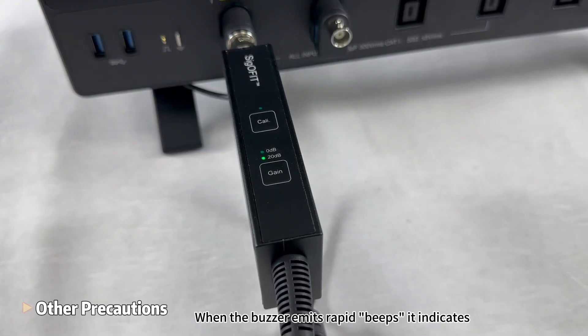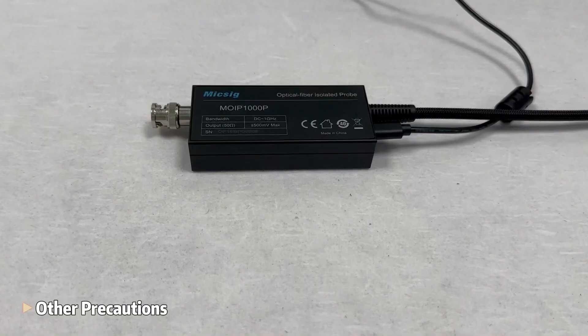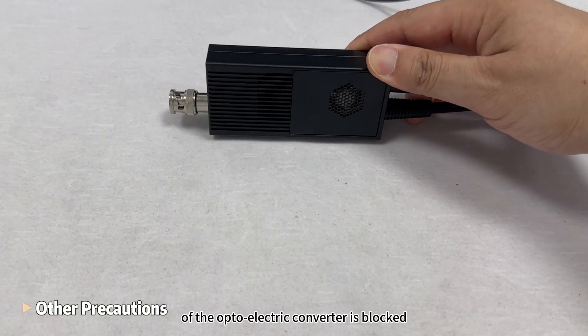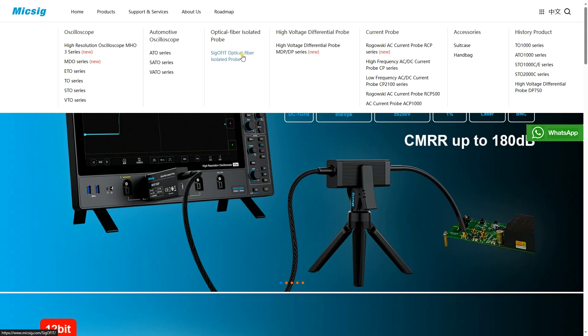When the buzzer emits rapid beeps, it indicates that the input voltage exceeds the range. If the buzzer emits a beep every 2 seconds, it signals that the optoelectric converter is overheating — check if the heat dissipation port is blocked. Visit our website at www.micsig.com to get more information.